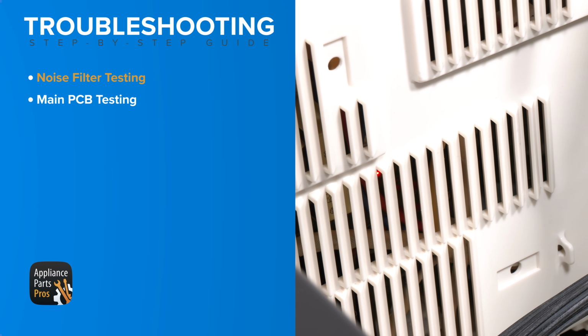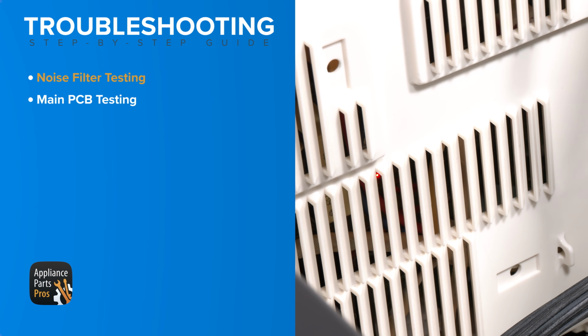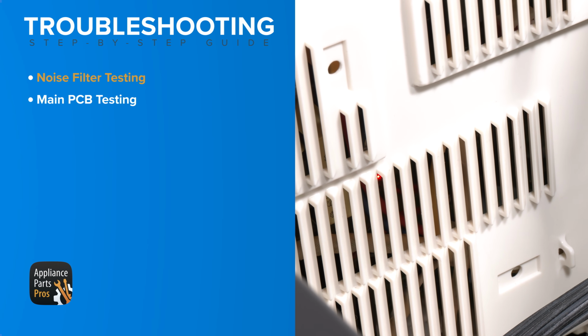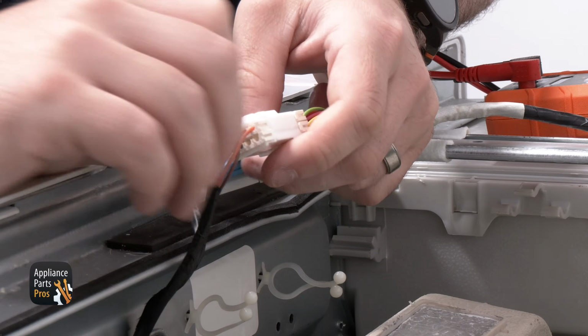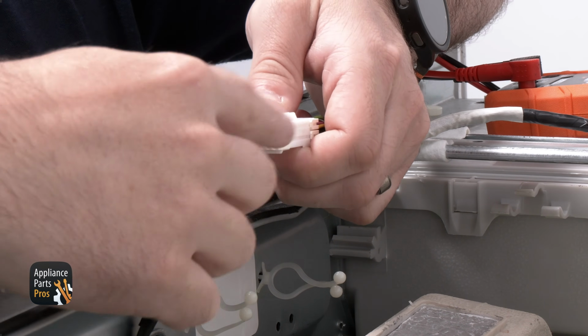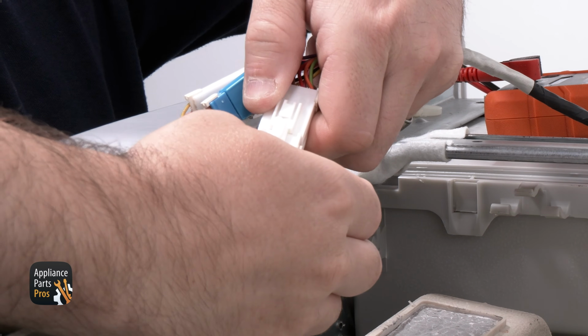Since we found 120 volts AC at the noise filter, we are going to look for an illuminated red LED on the main control. If the red LED is illuminated, we will need to check for voltage at the 8-pin, 6-wire connector going to the display control.